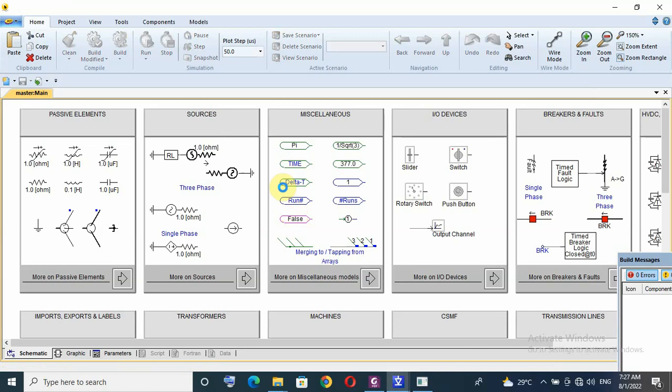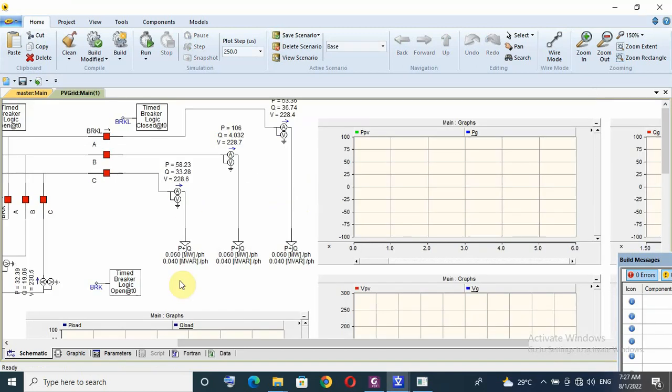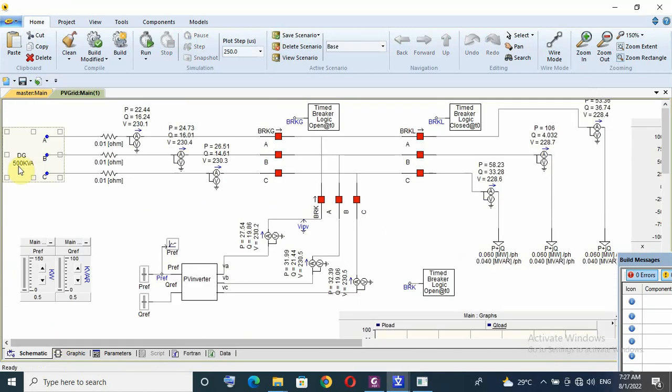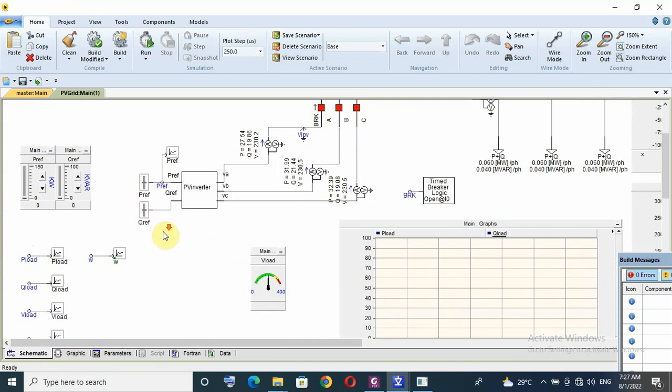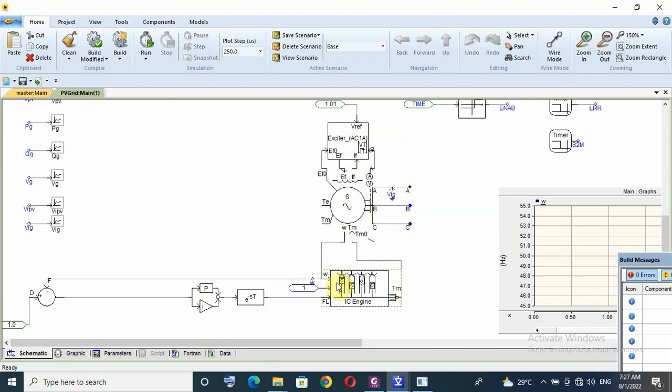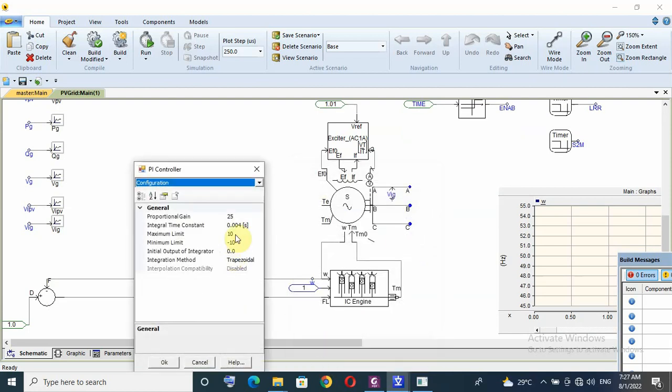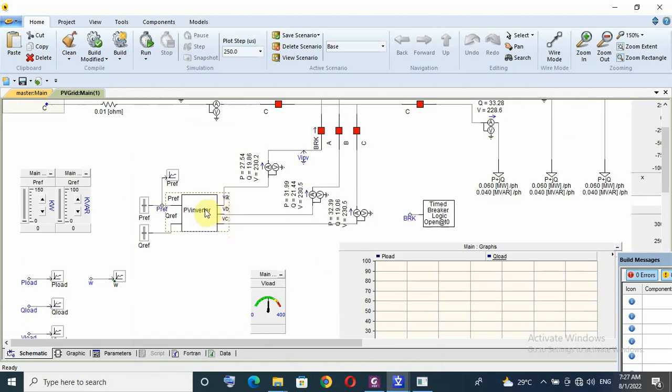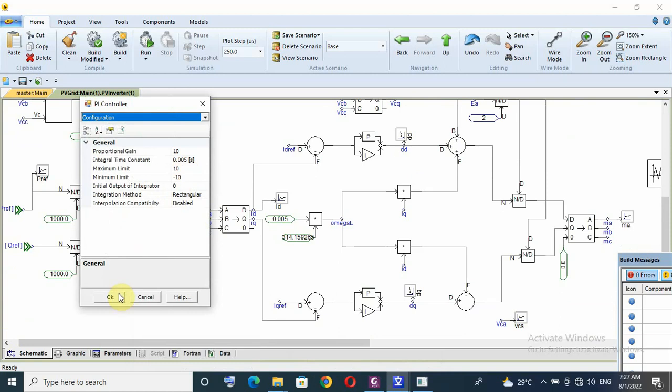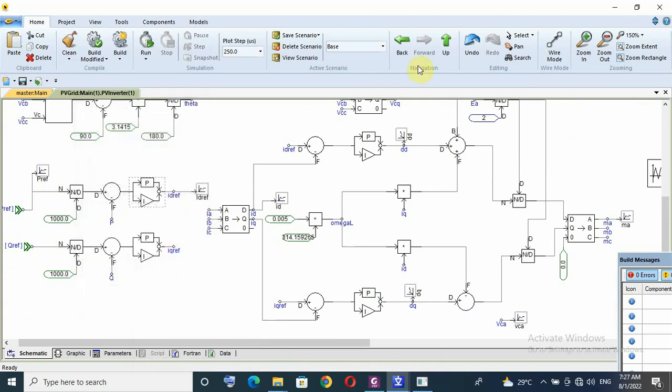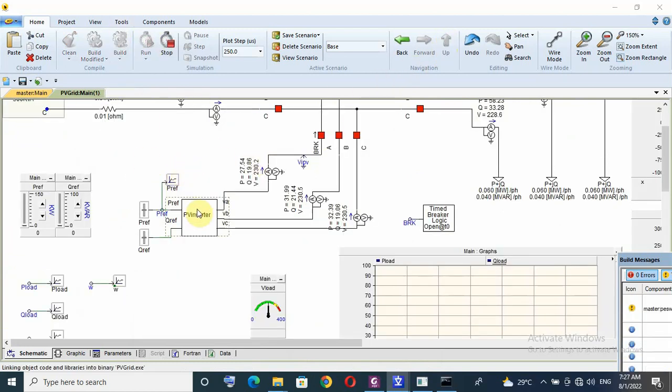I have 500 kVA DG, same inverter. This engine is 400 kW and this tuning same as before for inverter. The PV tuning also the same as for grid, so let us check the response.